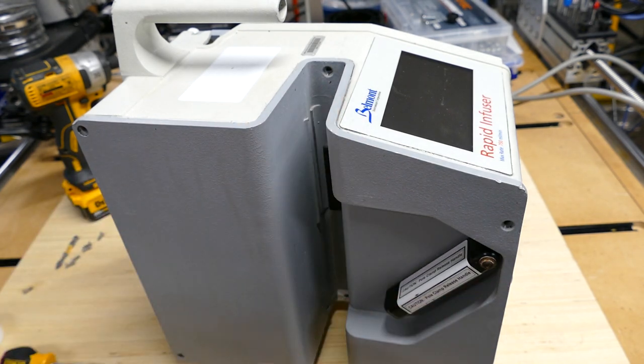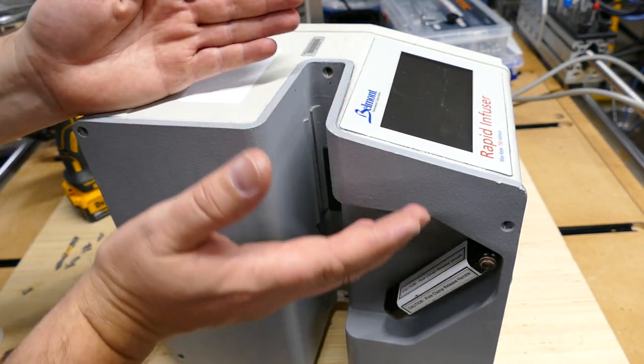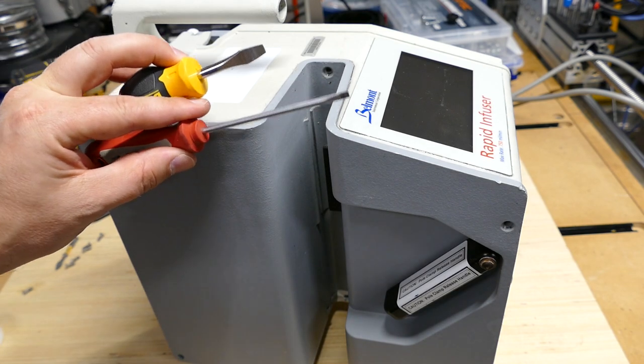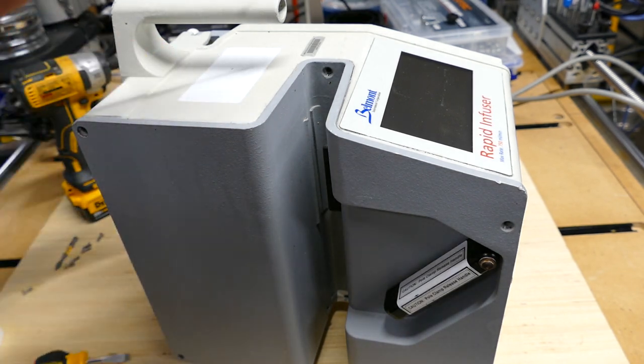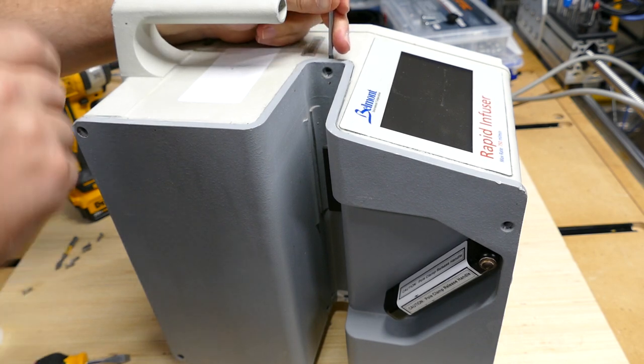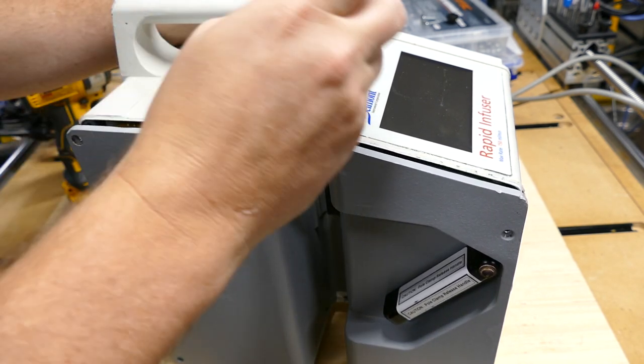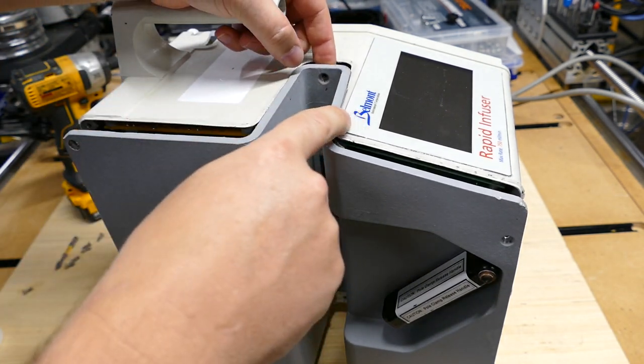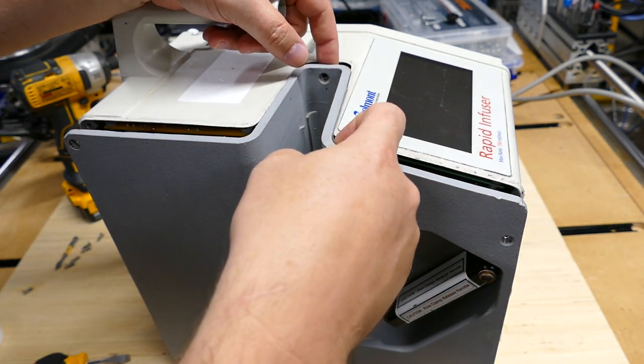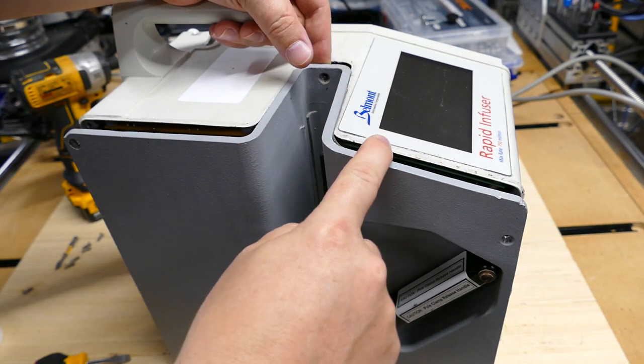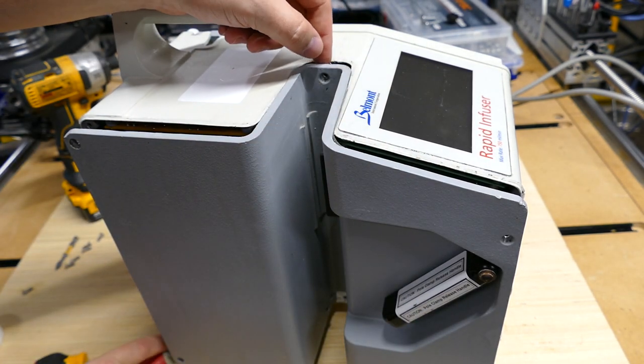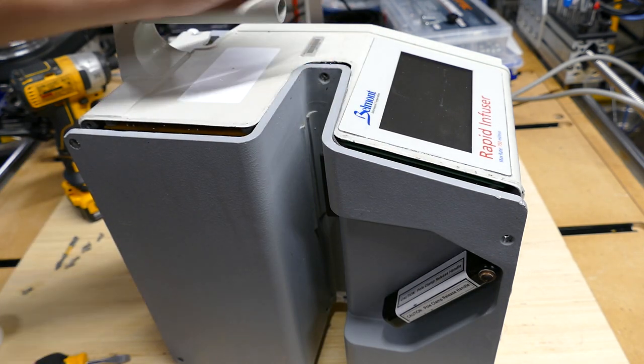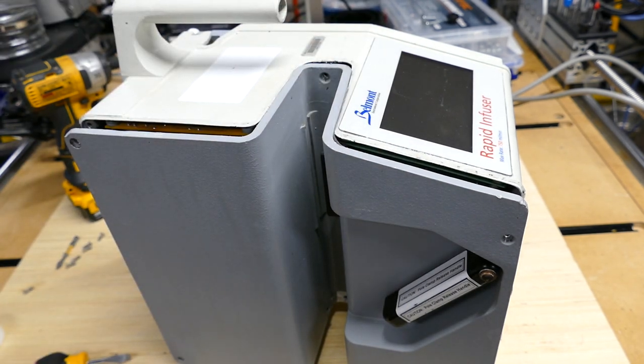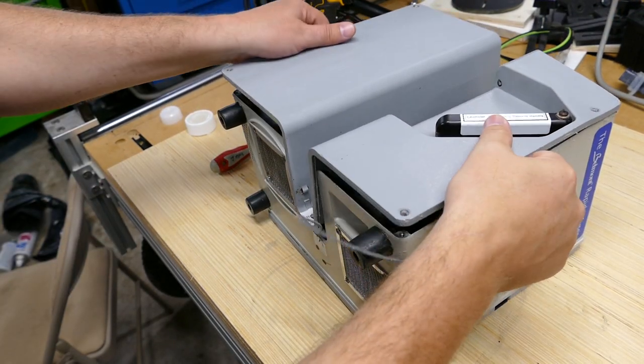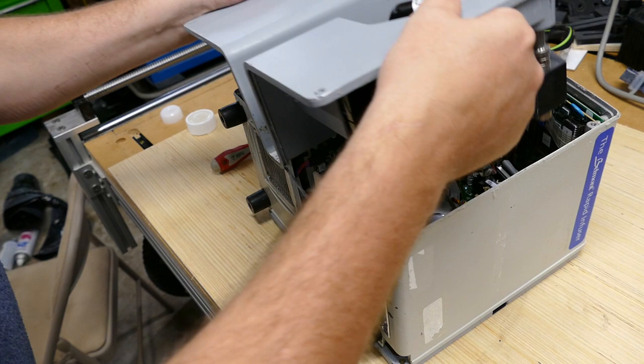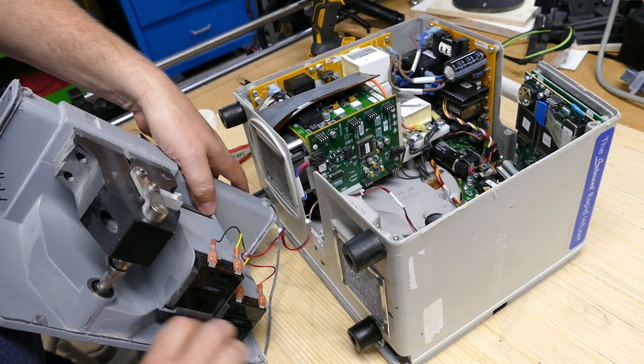Once you get the case screws out, the next thing that we gotta do is pry this clamshell apart. Remember kids, flathead screwdrivers are not pry tools. I like to start right up here at this midpoint, pop it in, just give it a light pry outward, and what you're going to do is break the silicone seal. There is also a rubber O-ring that goes in there, but more often than not, that rubber O-ring is long gone and they've replaced it with silicone. So we're going to go ahead and pull her apart. Once it's broke loose, I'm going to lift the cover off. You can see that rubber O-ring I was talking about right here.